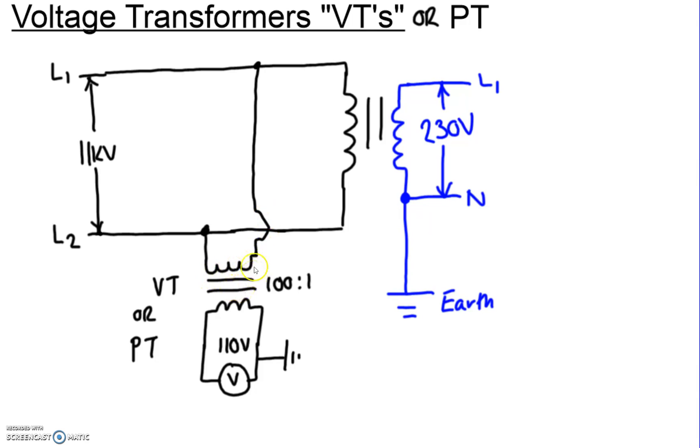So we want to measure the incoming voltage. But it's a little bit tricky when you've got 11 kilovolt because it's high voltage. The insulation needs to be bigger on the cables. The equipment needs to have higher voltage strength. So an easy solution to that is to use a voltage transformer.